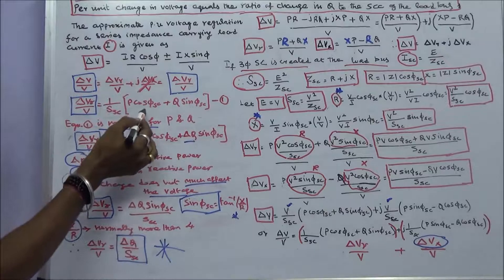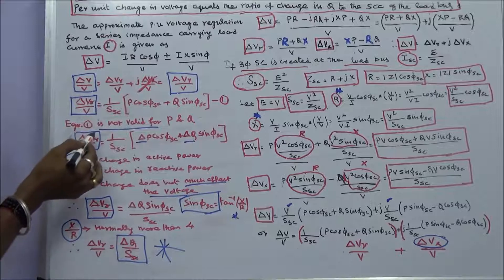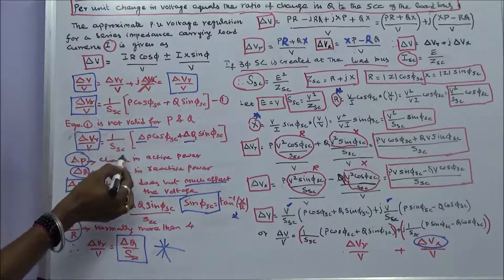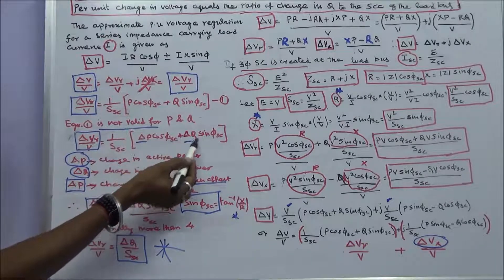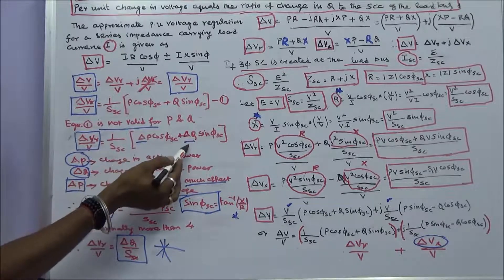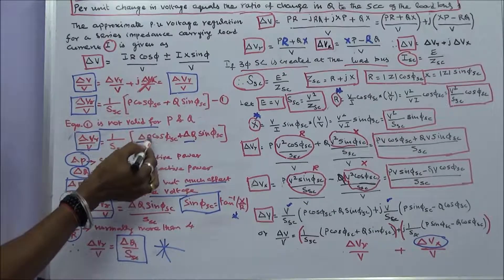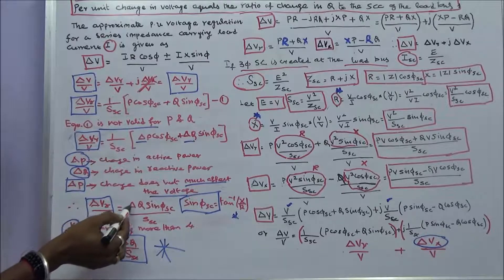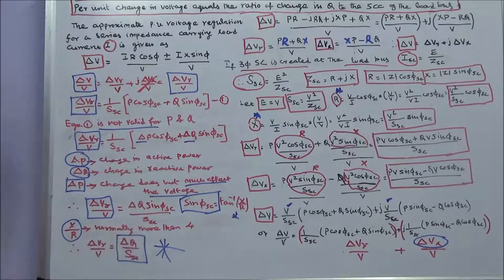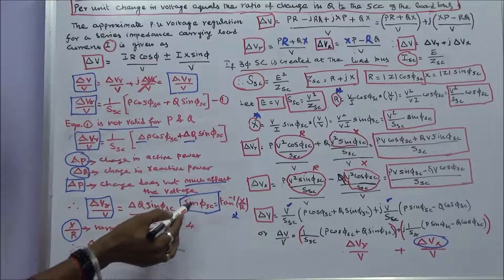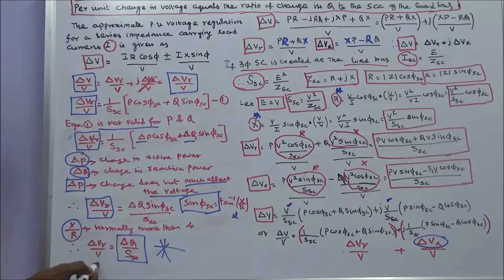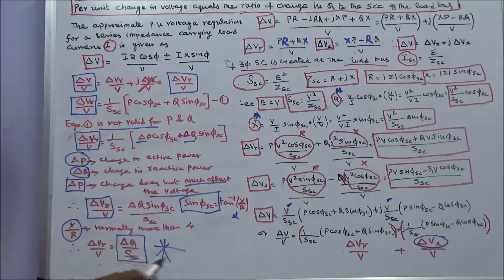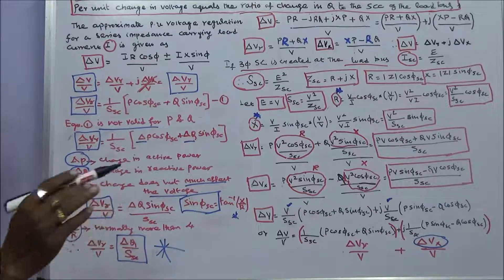Equation 1 is not valid for absolute values of real power P and reactive power Q, but for their changes. Therefore, delta V_R / V equals 1 divided by S_SC times [delta P·cos(φ_SC) plus delta Q·sin(φ_SC)]. Here, delta P is the change in active power. Since delta P does not significantly affect the voltage magnitude, we neglect it. Therefore, delta V_R / V equals delta Q times sin(φ_SC) divided by S_SC. Since the X/R ratio is normally greater than 4, sin(φ_SC) approaches 1. Therefore, delta V / V equals delta Q divided by the short circuit apparent power S_SC.